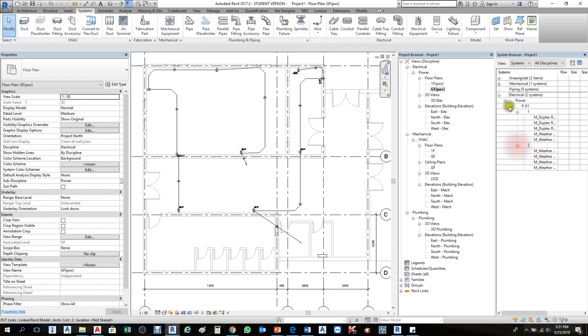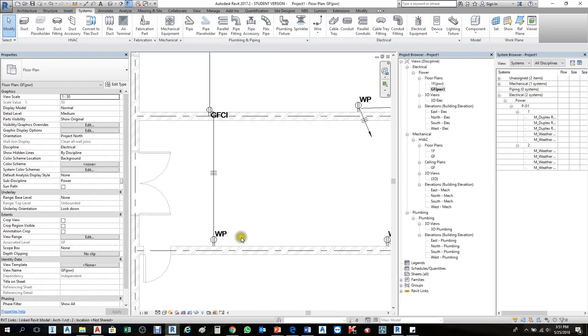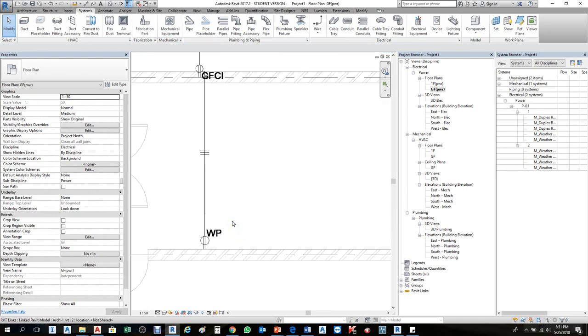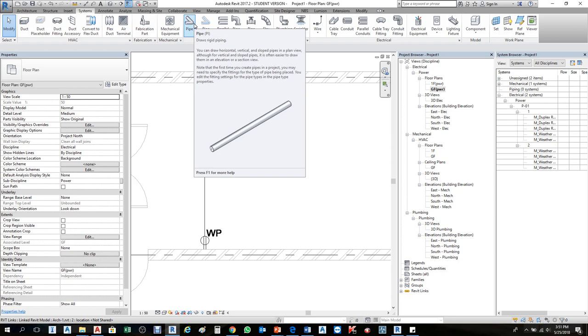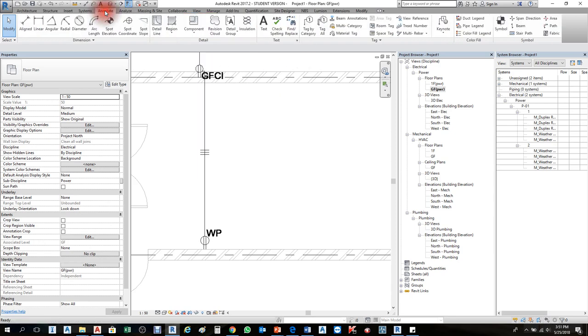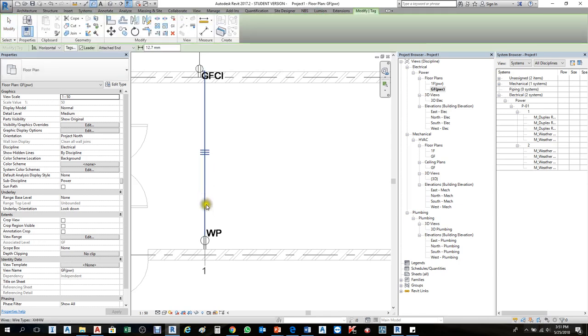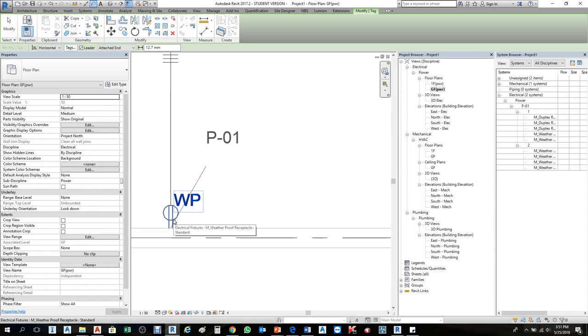Now, how to tag these fixtures. The shortcut is TG, or go to Annotate > Tag by Category or Tag All. I'll go to Annotate > Tag by Category, then click on the outlet wire. When I click the outlet it shows P01 — indicating which panel this outlet is connected to. Click and move the tag down to position it. Do the same for others, clicking the outlet and moving the tag label as needed.